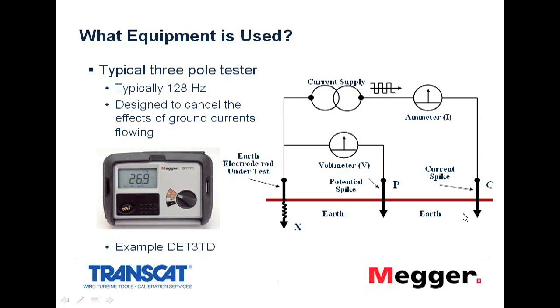Okay, I'm often asked whether or not it's possible to use other equipment. Well, where this varies predominantly from other instruments is how it injects the current. As you can see from the test source here, I'm injecting a square wave, and this is typically 128 Hertz. The reason for that is 128 Hertz is not a harmonic of 60 Hertz. Therefore, if I inject a current into the ground at 128 Hertz and phase lock my voltage measurement into that frequency, then I have a very good chance of ignoring any other stray currents flowing through the earth mass.